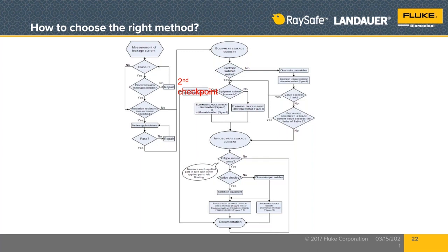So again, we have a decision point here: is it isolated, yes or no? All right. If it is isolated, then we get to choose either the differential or the direct method. It's up to us. As I said, if you're working for a medical device manufacturer in the field service organization, the quality manager should be requiring that the direct method be used. However, they may or they may not be. So that's the second checkpoint.